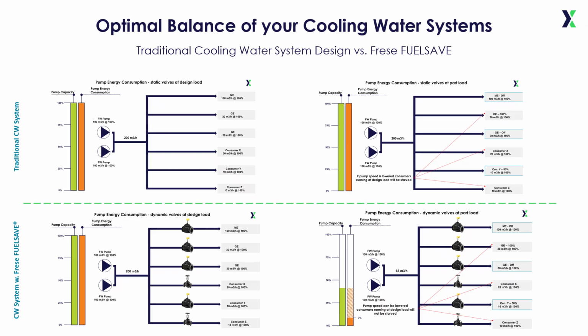Only in the scenario to the bottom right, pressure-independent valves at part load, it is possible to harvest the potential savings that are given by the operational profile of the vessel. This without compromising safety on board. The critical consumers will always have their design cooling capacity available if need be.